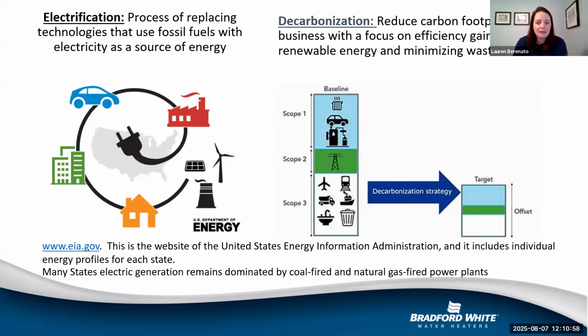Yes. And I think the thing too that's been going on with heat pumps is that we're seeing a lot of inquiries come in and building owners hear about the cost efficiency for a heat pump and they want that to be installed because it is incredibly cost efficient. However, the upfront cost is very expensive. It's often 4 to 7 times the cost of a standard electric water heater. So do you want to pay that upfront cost to get the payback in the end?